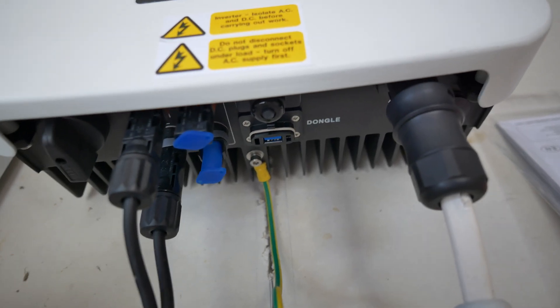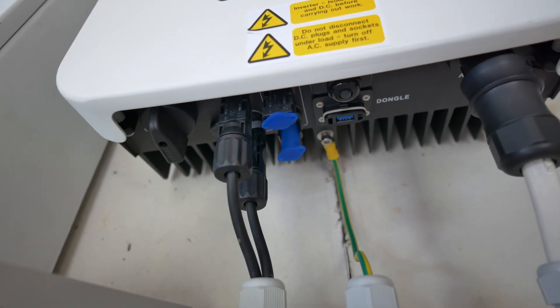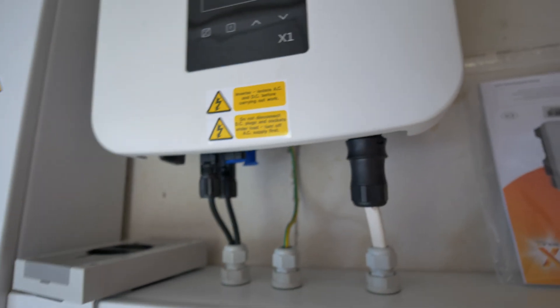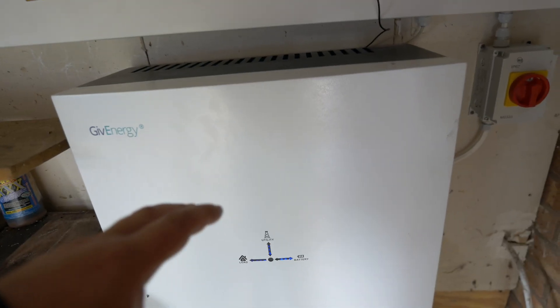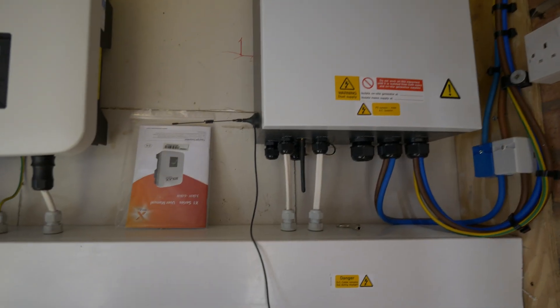On the underside of the Solax there, you can see we've got our earth bond running up to bond the equipment. We just use the one string because this is an optimised array, and then we've got our main feed-in onto the plug here. If this was a hybrid system, you would have your DC cables out of here to the battery — but the GivEnergy system is AC coupled, so the AIO has its own inverter to convert the stored power in the batteries to AC, and then it feeds it into the gateway itself.